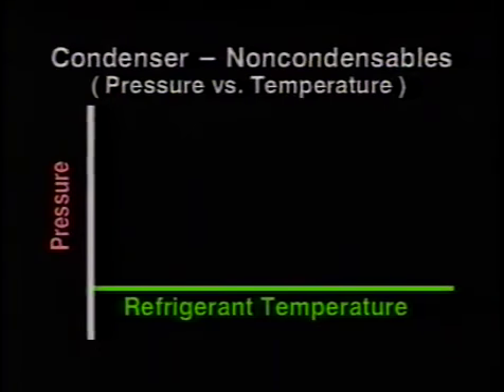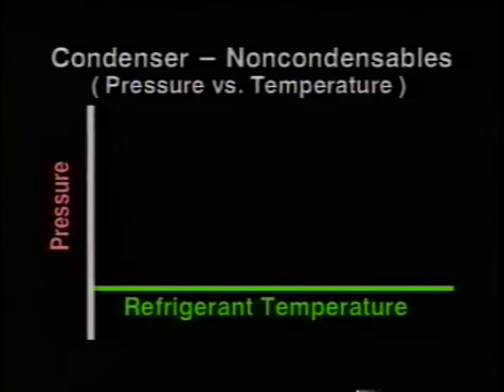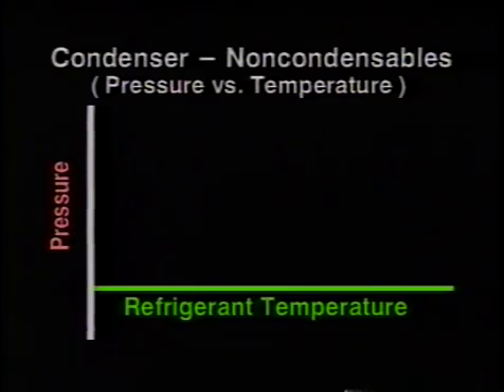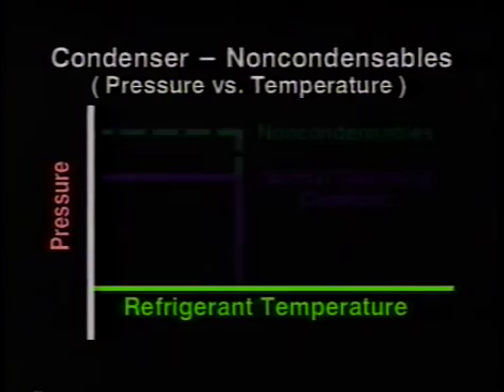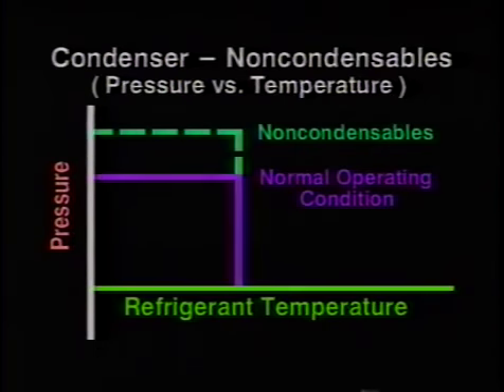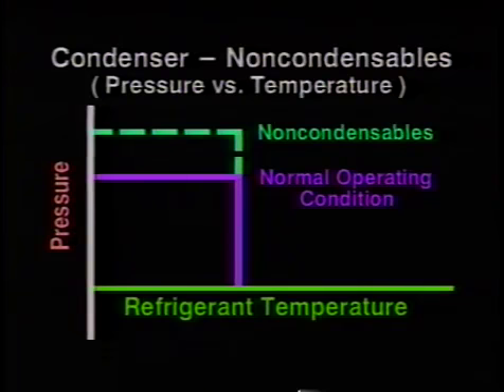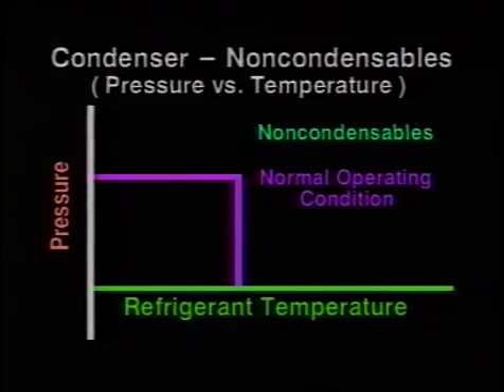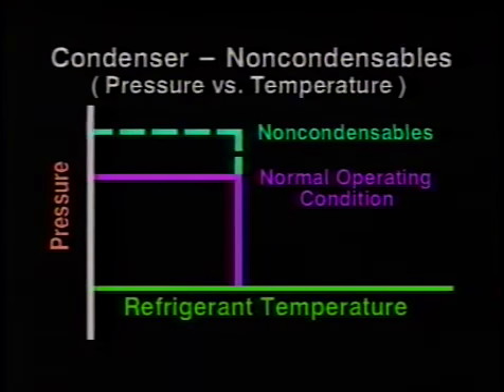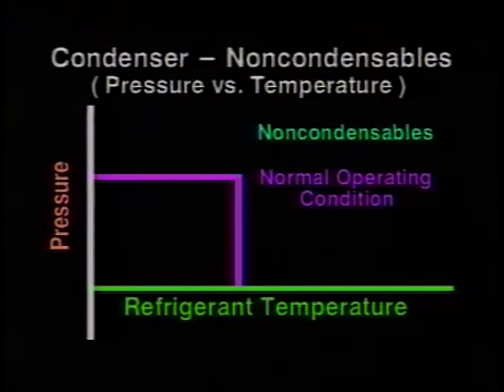A comparison of the saturated liquid temperature to the condensing pressure will confirm if the condenser has non-condensables. If non-condensables are present, the saturated liquid temperature at the condensing operating pressure will not agree to the pressure-temperature relationship. With non-condensables in the system, the indicating pressure will read higher than the pressure corresponding to the actual liquid temperature.